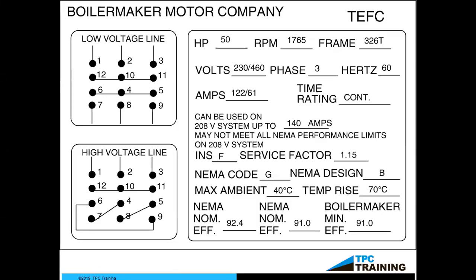If I wanted to go with the low voltage, then I would connect those windings in parallel. And when I did that in a parallel circuit, the voltage stays the same. So I would still have 230 on one winding and 230 on the other. But because of the different configuration, either series or parallel, that allows me to have the ability to connect it either into a low voltage or a higher voltage.